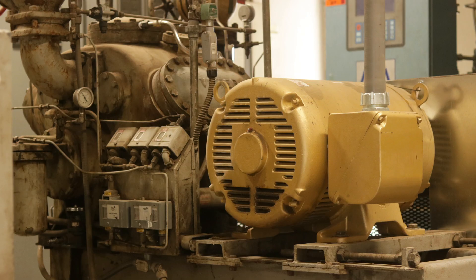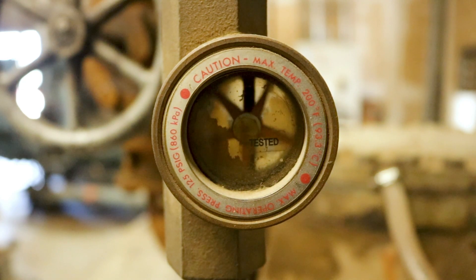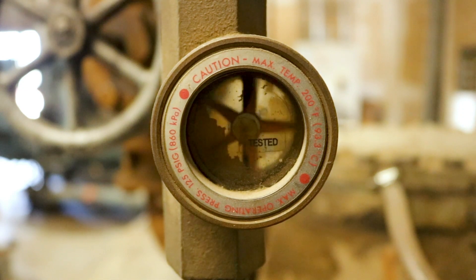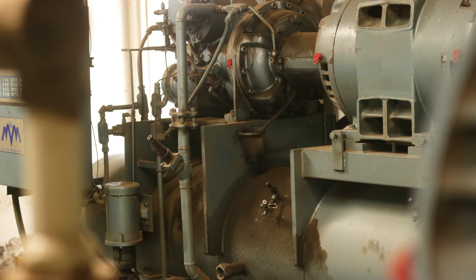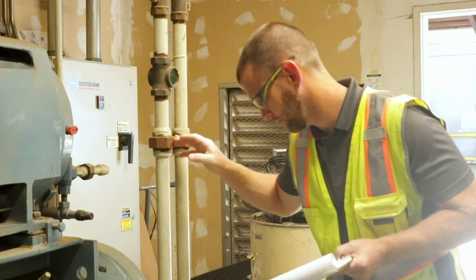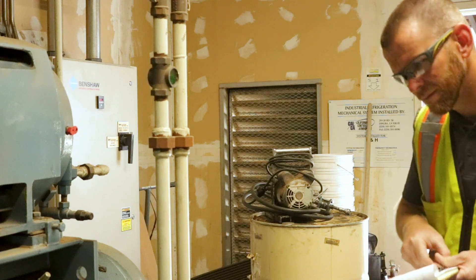The category of oil cooling and cooling medium are the next sections on the checklist. This reciprocating compressor is water cooled, so the "other" and "water" boxes would be checked. This screw compressor is also water cooled but uses a shell and tube oil cooler, so "shell and tube" and "water" boxes would be checked.